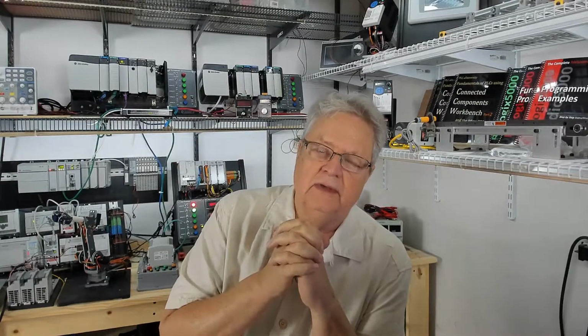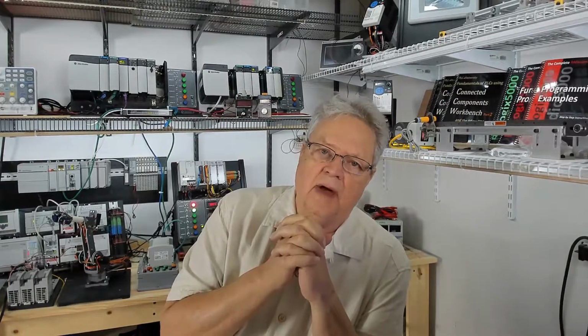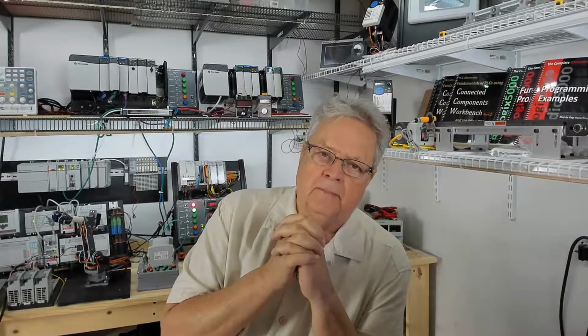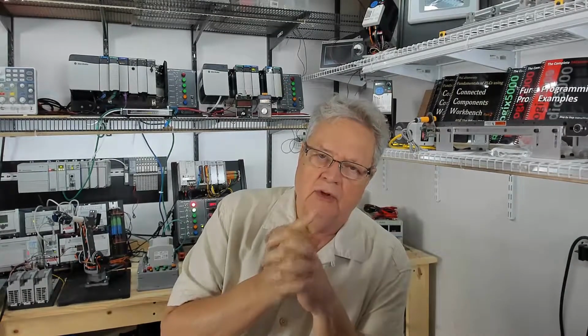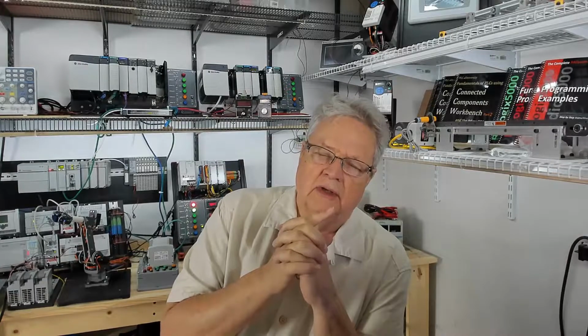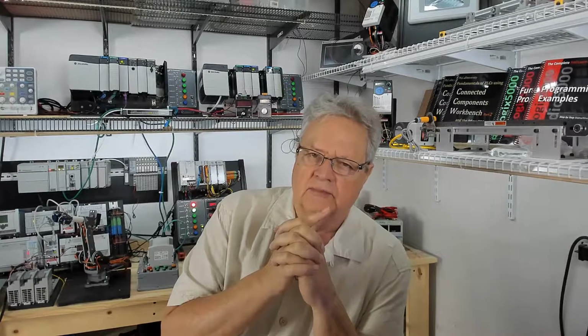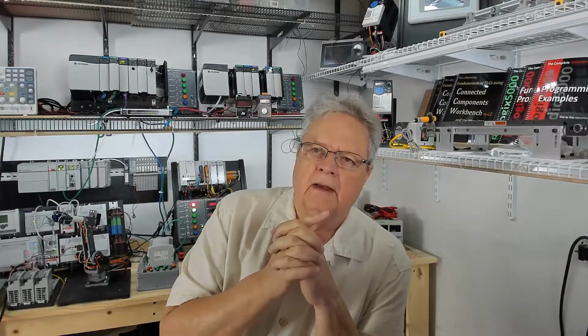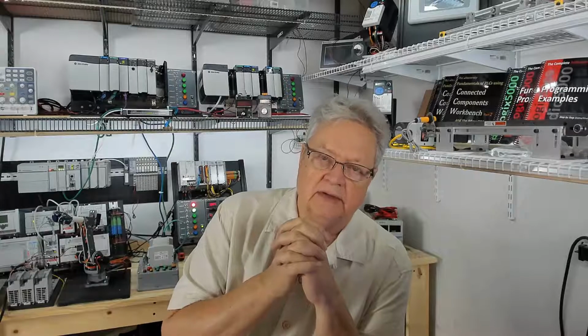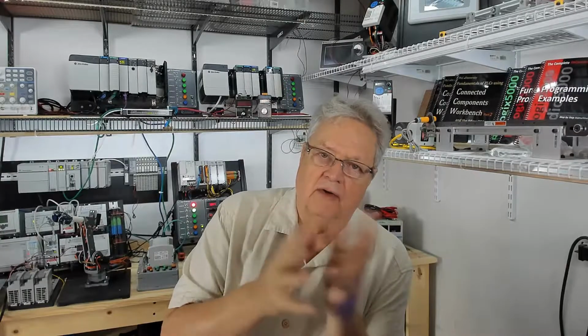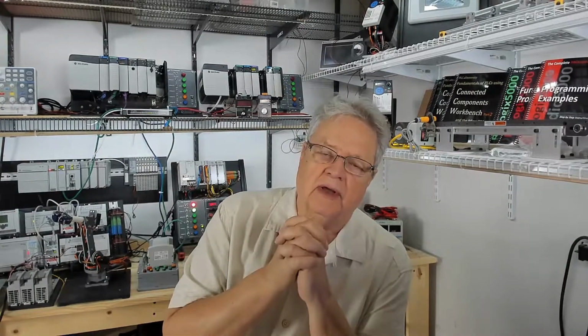As you know, the I/O modules, all modules on the backplane 1756, have an RPI, requested packet interval. Remember, those modules communicate with the processor on their own hook, so to speak. Not entirely. Let me explain. When you add modules to the backplane, the virtual backplane in your project, you have to add all those modules before you can use them in programs.